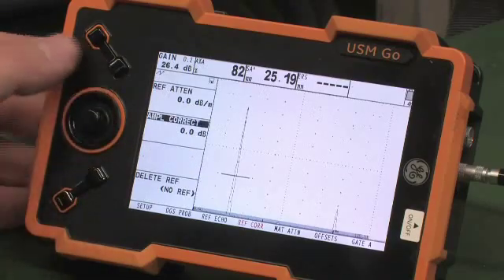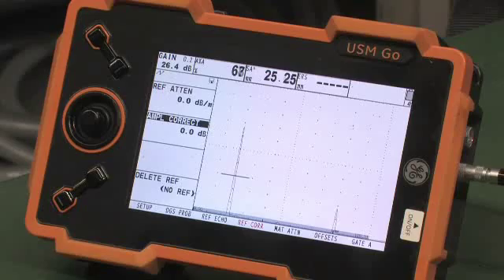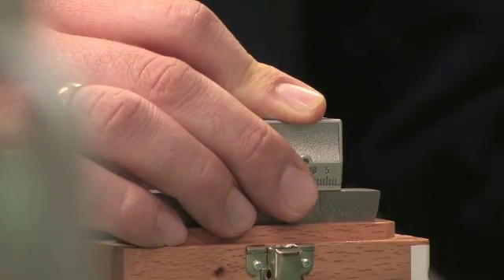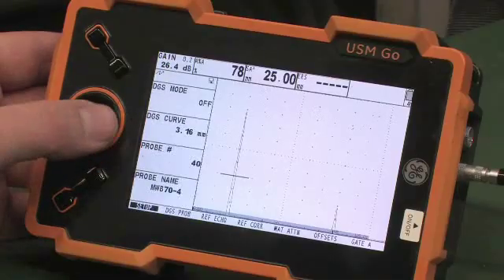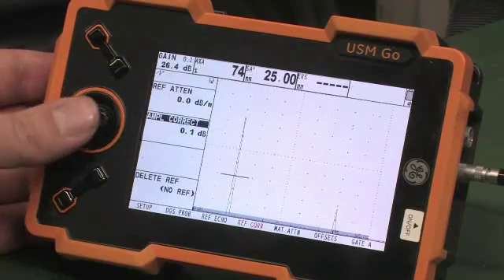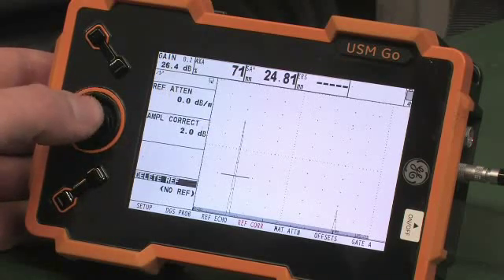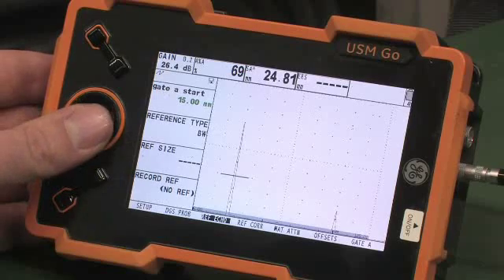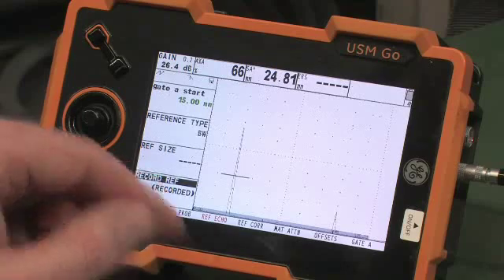If you use a calibration block, please make sure that you have the respective correction factor and that this correction factor is entered in the appropriate field in the DGS section. Also, make sure that the correct probe type is chosen and go to the Ref Echo menu item. Double-check that your signal is optimized and that you have correctly positioned the gate over the signal. You may then record the reference echo.